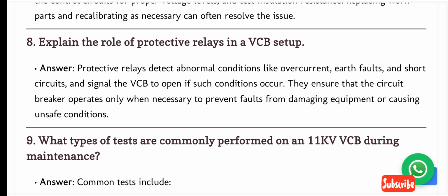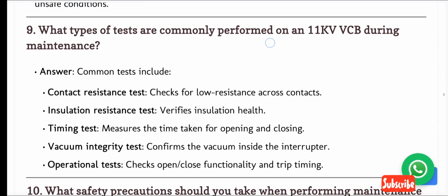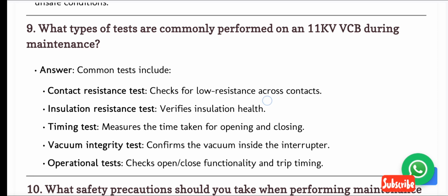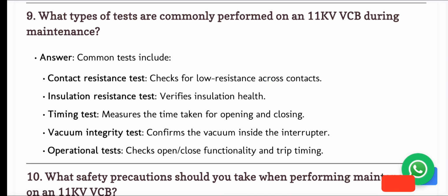Answer. Protective relays detect abnormal conditions like overcurrent, earth faults, and short circuits, and signal the VCB to open if such conditions occur. They ensure that the circuit breaker operates only when necessary to prevent faults from damaging equipment or causing unsafe conditions. 9. What types of tests are commonly performed on an 11 kV VCB during maintenance?